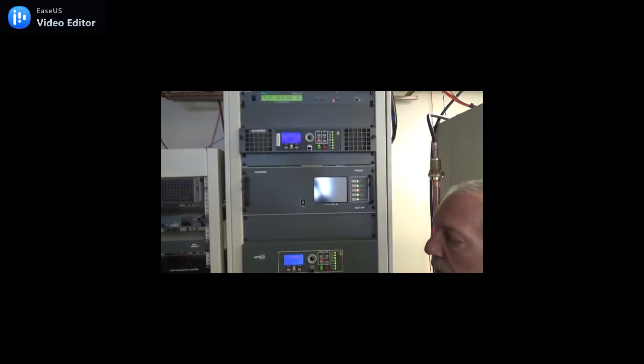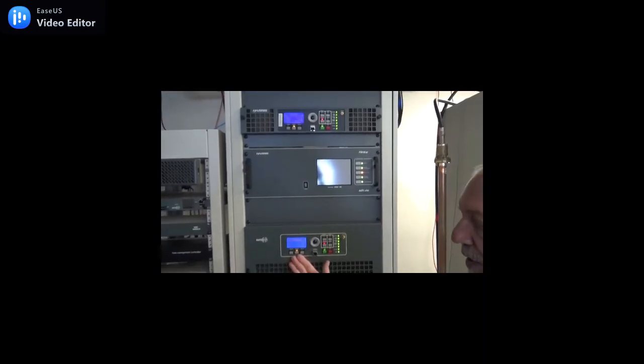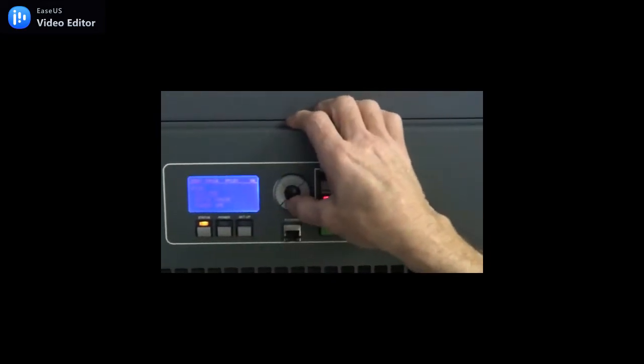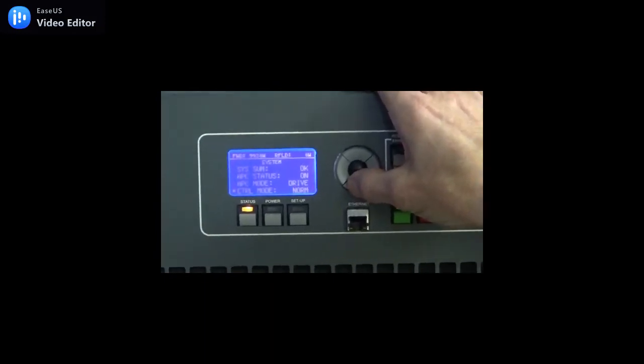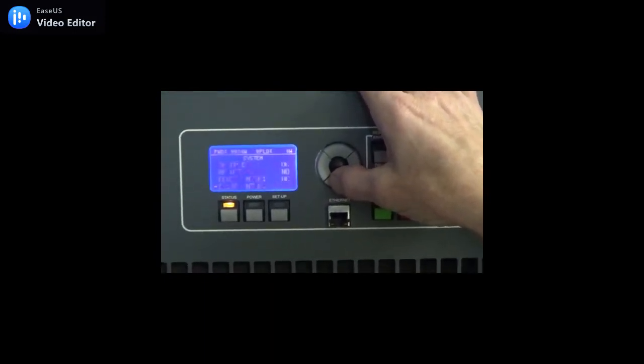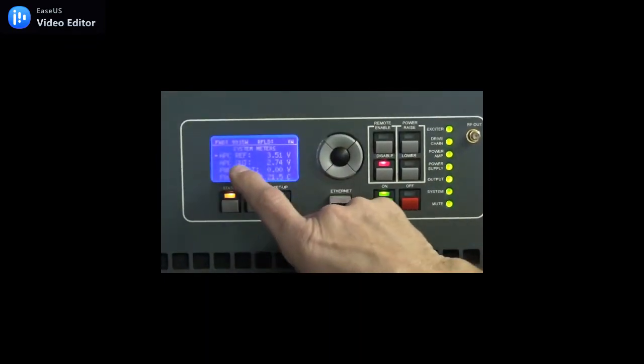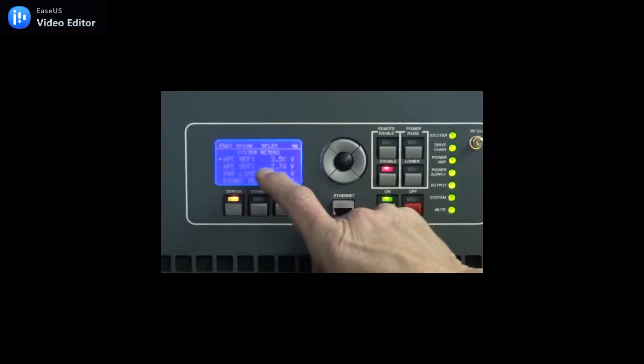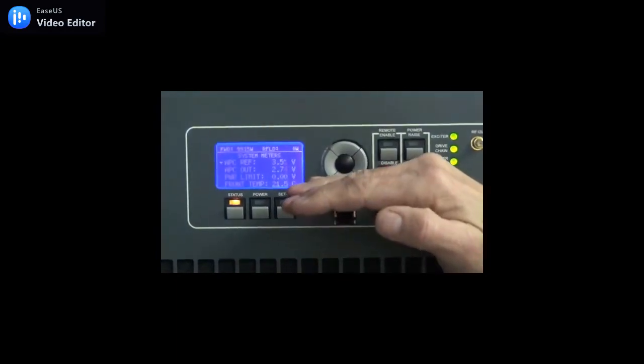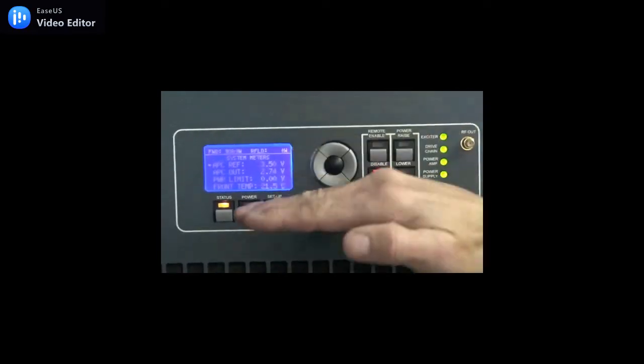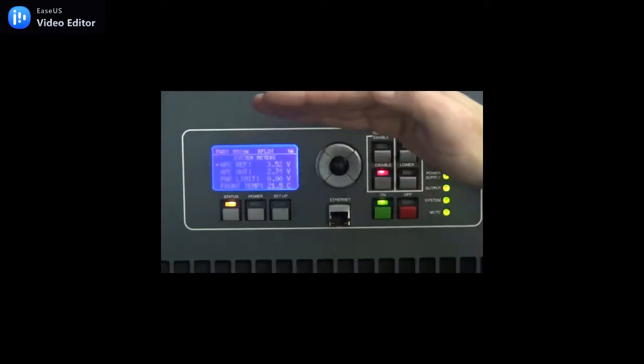So that will ensure that the transmitter does not overdrive or ramp up past where it needs to and cause any kind of a problem. So we're going to come down to the transmitter front panel, and we're going to go into status. We're going to scroll down till we get to system, and then we're going to go to system meters. Enter. And now what we're going to look at is this APC output voltage. The APC output is what the transmitter is sending to the exciter to tell it to raise or lower power. So we don't want that to overdrive rapidly, so we're going to set a limit for that in the system.